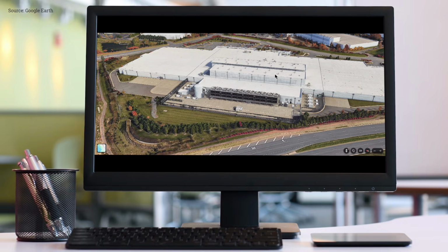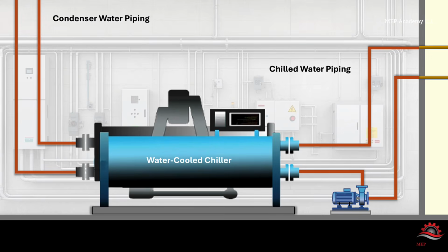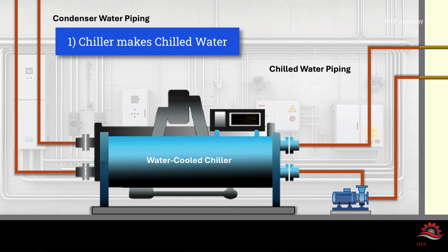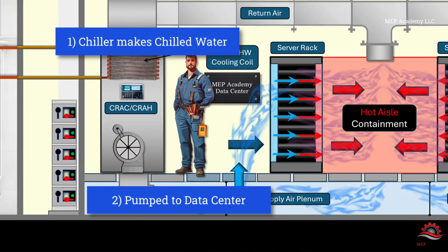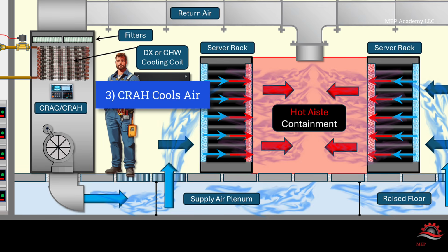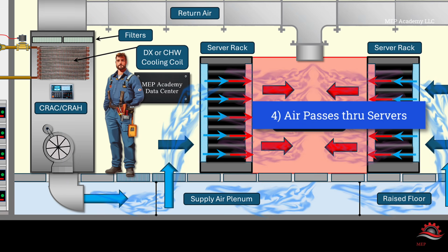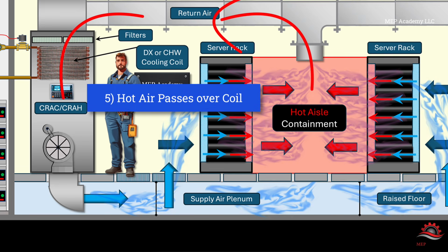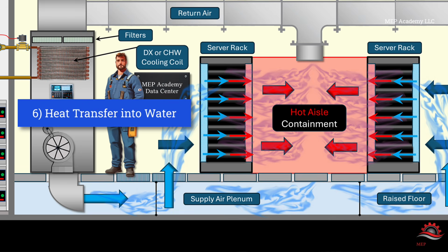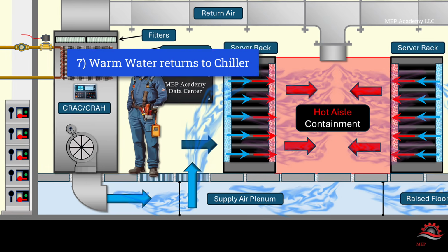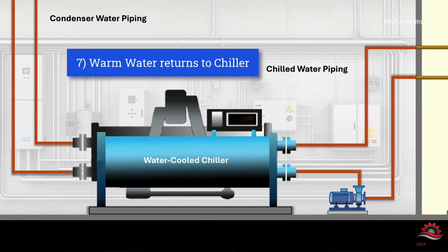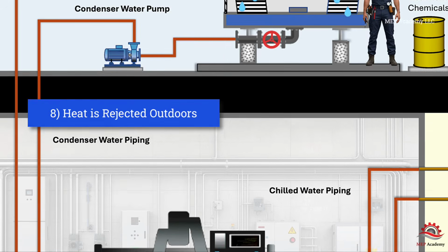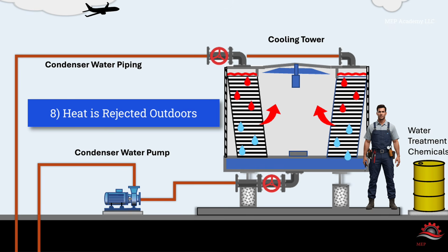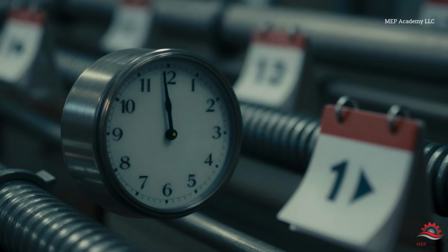Let's walk through the full cycle in a simple sequence. Step 1. The chiller produces cold water. Step 2. Pumps send that chilled water into the data hall. Step 3. CRAH units use that water to cool the air. Step 4. Servers absorb that cooled air and generate heat. Step 5. Hot air returns to the CRAH units. Step 6. Heat transfers into the water. Step 7. Warm water returns to the chiller. Step 8. Heat is rejected outside, and this loop runs continuously, every second of every day.